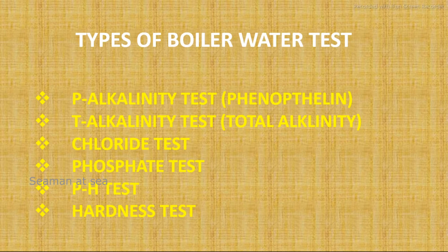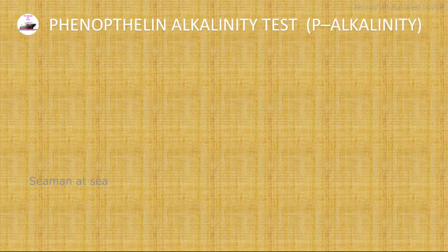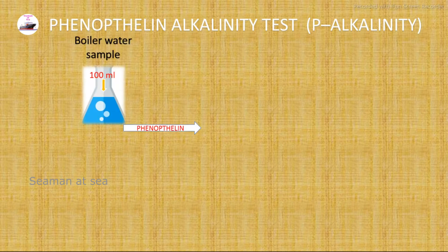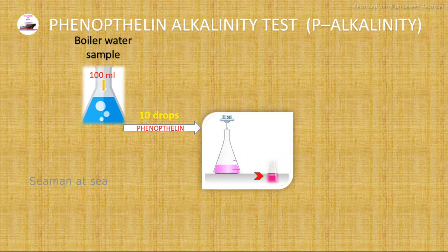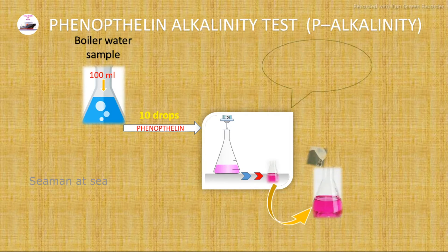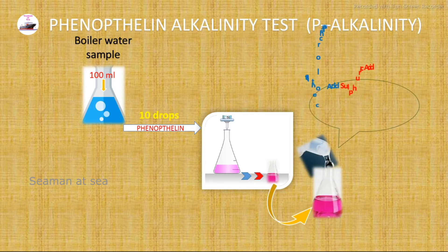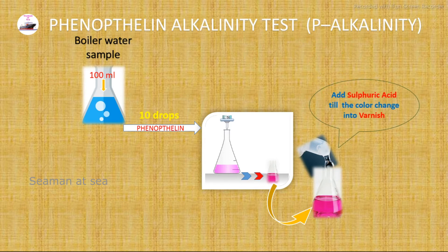Now we will see the testing procedure for each test. For the phenolphthalein alkalinity test, we have to take a boiler water sample of 100 ml. Once we have the 100 ml sample, we add 10 drops of phenolphthalein. The color will change to pink. Then we add sulfuric acid until the color changes to vanish, and we stop adding the sulfuric acid.